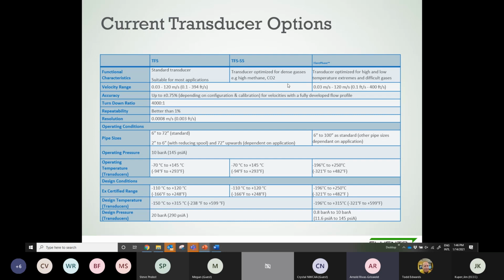When it comes to the different meters, I mentioned you have the standard transducers, but as we get through different applications, we see gases that are more challenging to send the signal through, and those are typically, especially CO2. Sometimes when you have really high methane, especially 100% methane, like LNG plants and stuff like that, you see this challenge. So we have the ability to use a different set of sensors that has enhanced signal processing and a stronger signal to be able to deal with those. The other specifications are quite the same, but these will have a signal strength at a different level that will allow you to deal with those cases.